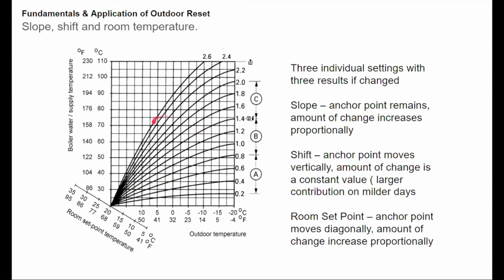Okay, but it allows me some way to anchor the curve at another point. And a lot of times the shift happens if somebody complains about the room temperature dropping or not being comfortable just under the mild days. Okay, so from an adjustment standpoint, you have a slope, you have a shift, and you have a room temperature set point. And through these three separate adjustments, it allows you really to tailor the shape and the location of the curve to meet the requirements of the home under a wide variety of conditions.